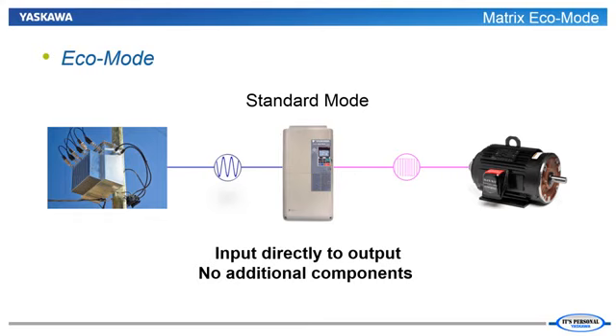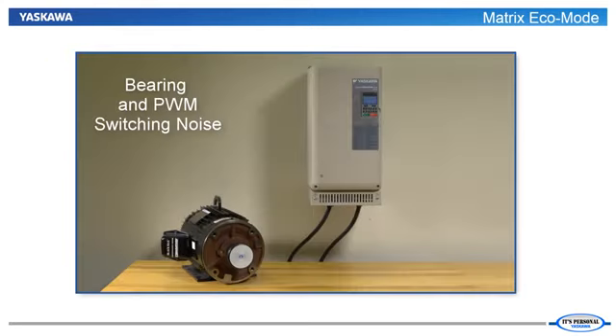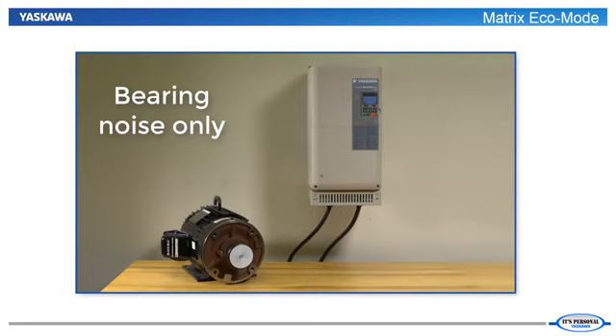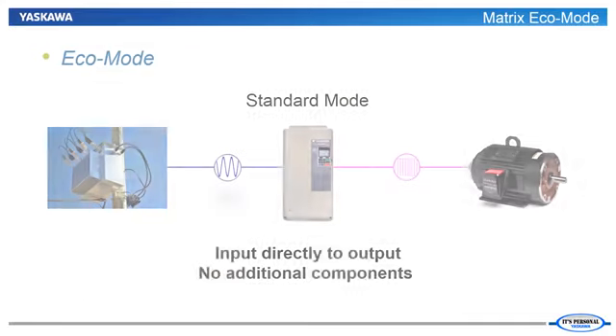Using the eco mode function, the matrix can be programmed so that when it is running the fan or pump near line frequency, it will simply pass the incoming sine wave power through untouched. When the application no longer needs to run up near line frequency, the matrix will transition back to PWM switching and run the fan or pump at whatever speed the application calls for. Eco mode eliminates audible motor noise, drive switching losses, and high frequency noise like common mode and differential mode noise. Going into eco mode can improve drive efficiency by 19% on average.